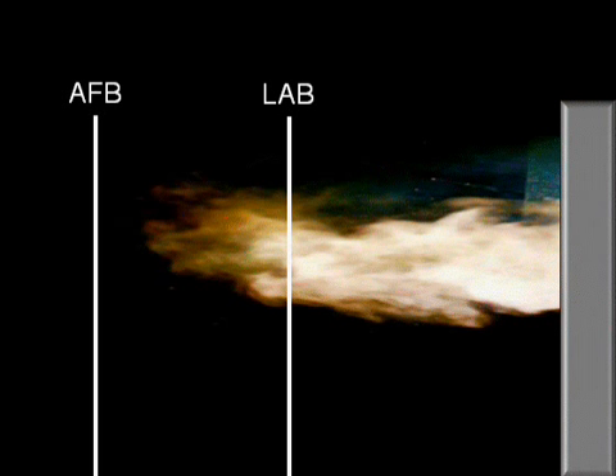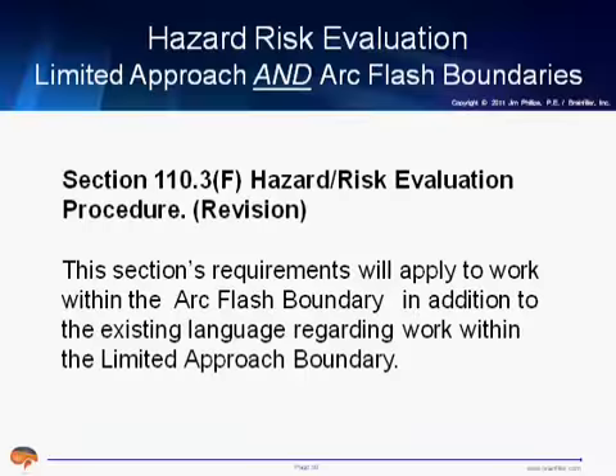And that's fine as long as, if you had an arc flash, it was a low enough magnitude of energy that the arc flash didn't reach the limited approach boundary. But the problem that you have, and this new language is clearing this up, is if the arc flash happens to be a significant arc flash with a significant amount of incident energy, it's possible, and in fact this does happen, that the arc flash can go past the limited approach boundary, and then the arc flash boundary is actually further back. And so you want to make sure that you're behind whichever one is the greater. Otherwise, in this case that I have up on the screen, if unprotected people were outside the limited approach boundary and this event occurred, it would be the proverbial bad day.